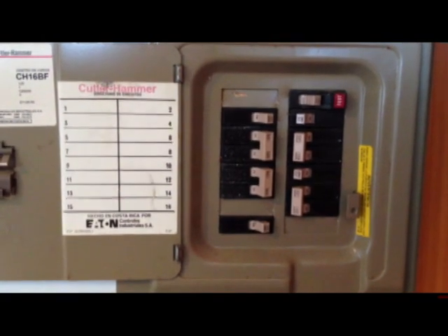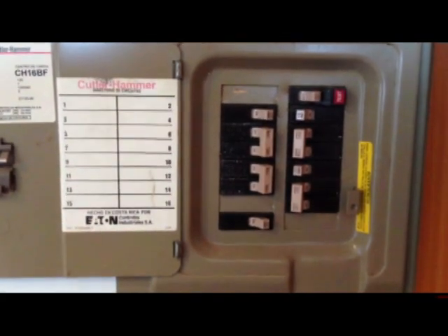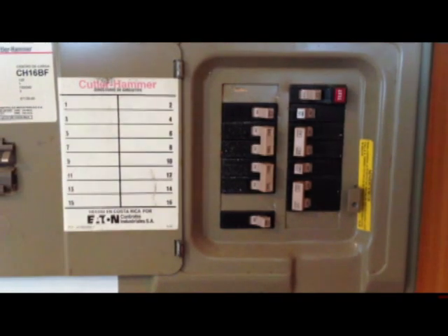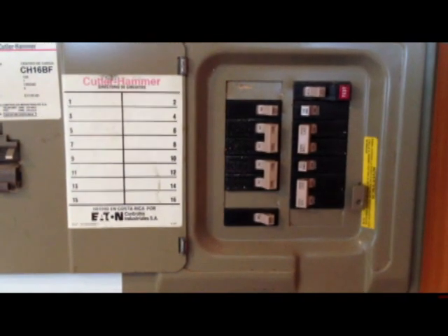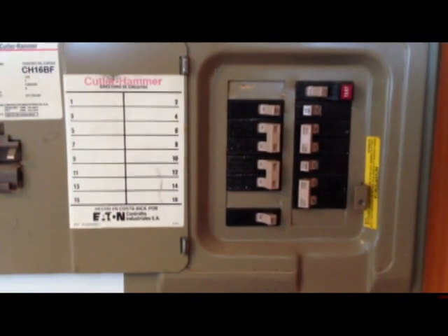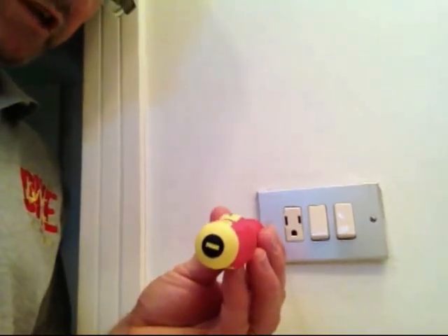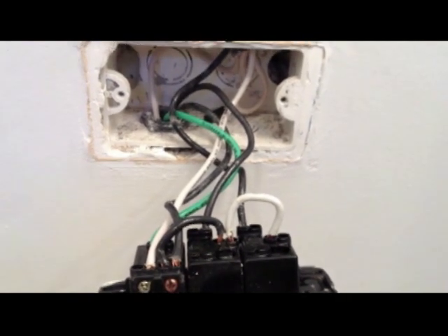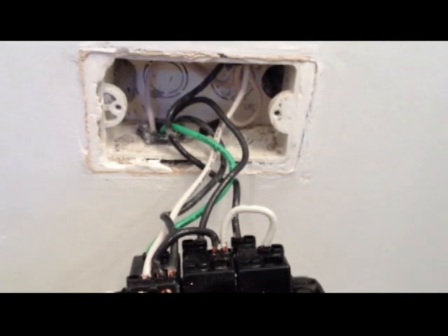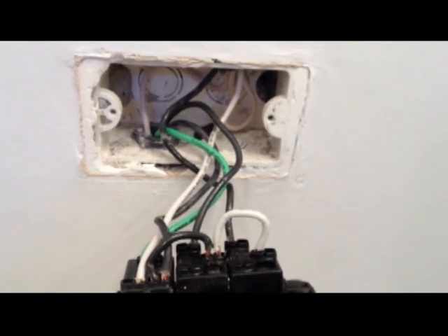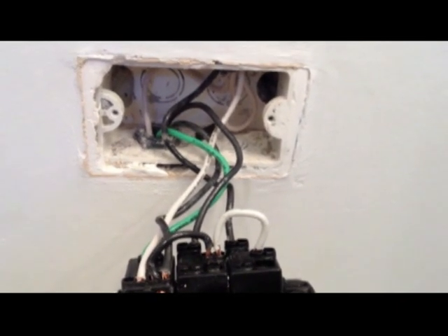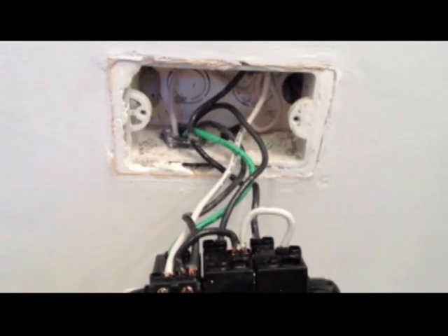So I've got the breaker off now, and we'll begin to take apart the receptacle and switch combination and see if I can find any cause for that bad connection and the buzzing and the dimming of the lights. So first things first here, we're going to remove this faceplate. Okay, here we are. I've got the device pulled out of the box, and I'm actually quite impressed with the wiring here. That box is mounted out to the surface as it should be in a concrete wall. There's conduit run, so they've run conduit and wires. They have a ground to this GFI receptacle, which is nice.